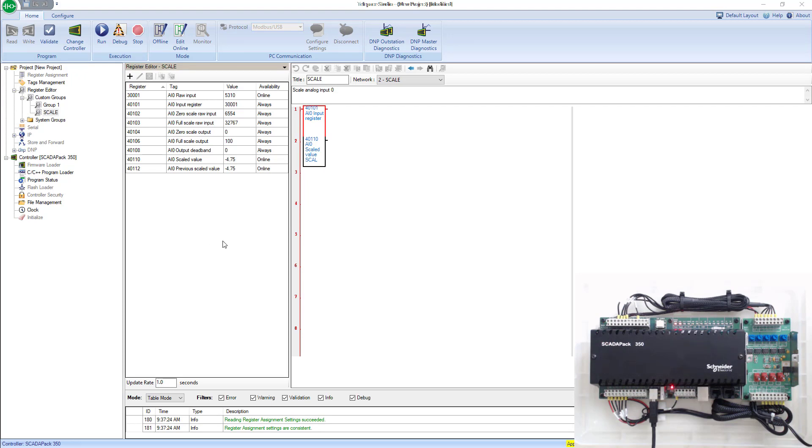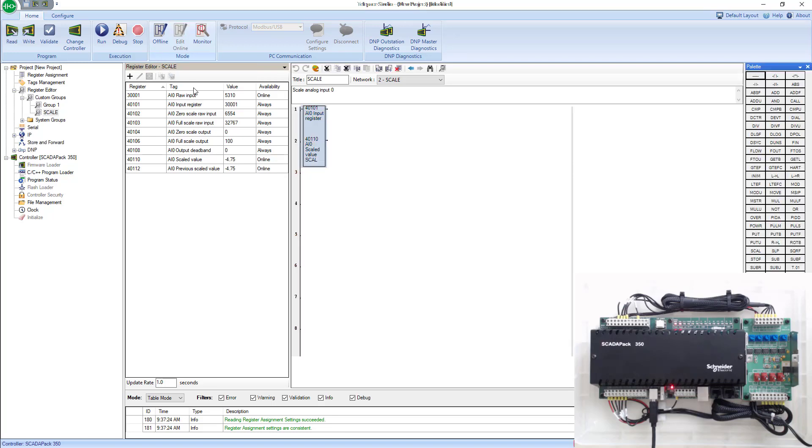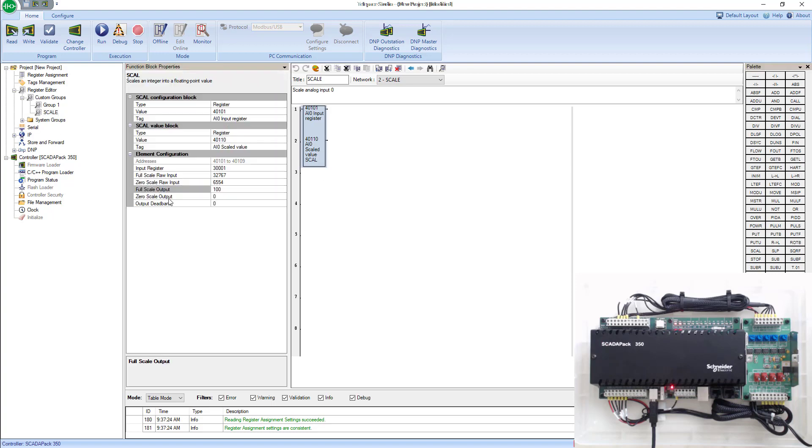One last thing we're going to do before we finish this lab is change the scaling. Initially, we did it from 0 to 100%, which you typically don't see. We're going to change the scaling to 0 to 6,000 psi. So we'll go in our block here. We can just hit edit online. We're going to make a quick change. Instead of the full scale being 100, we're going to change this to 6,000.